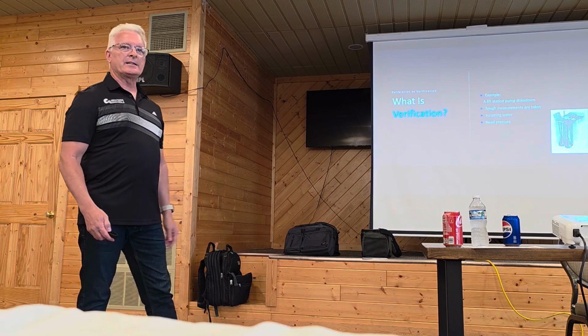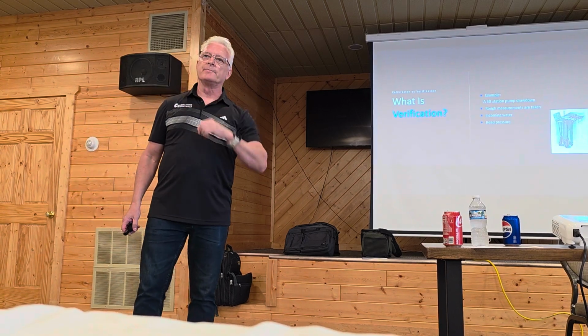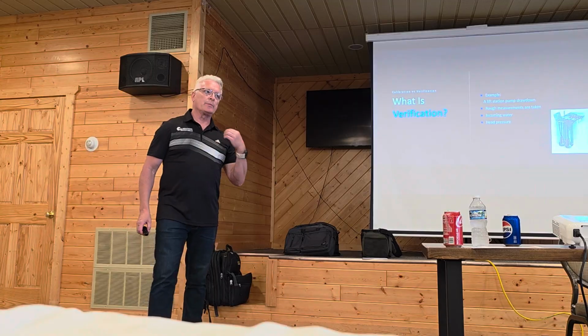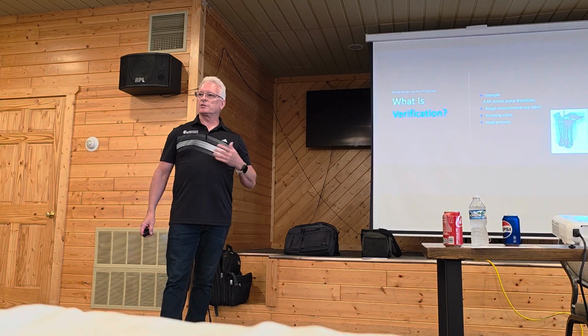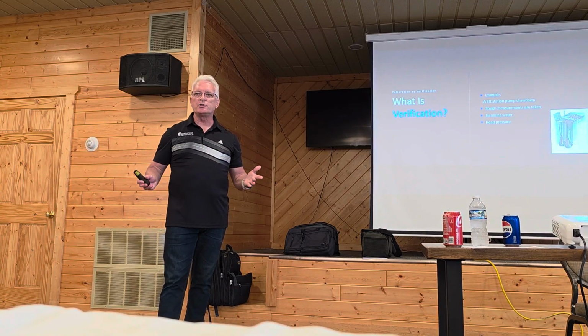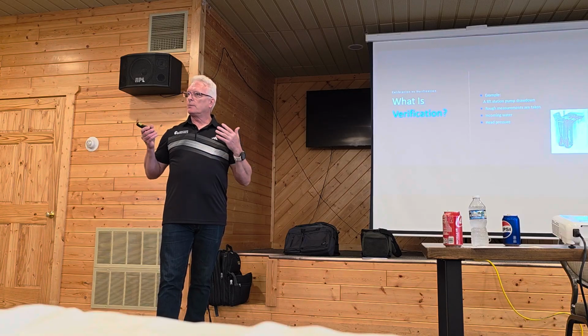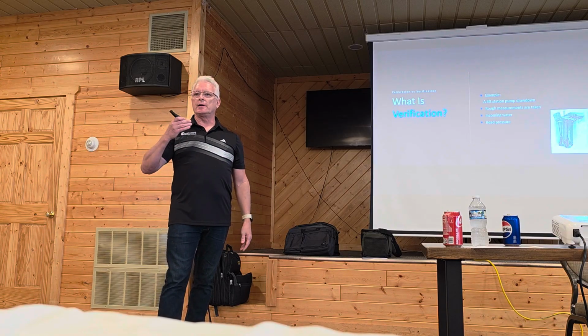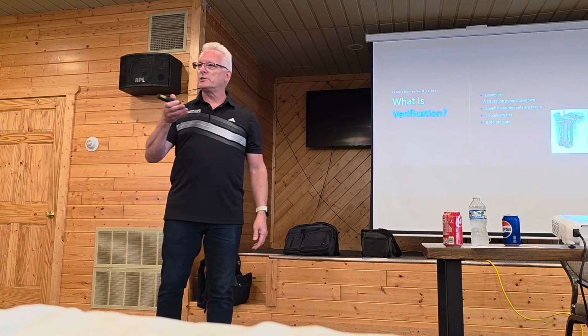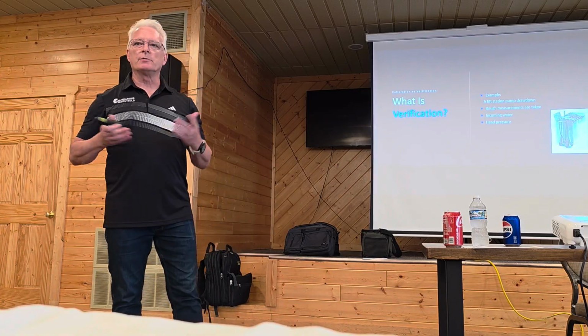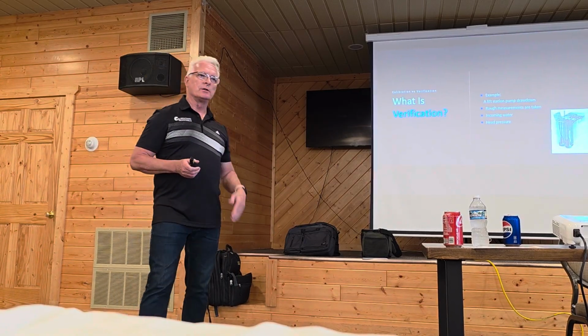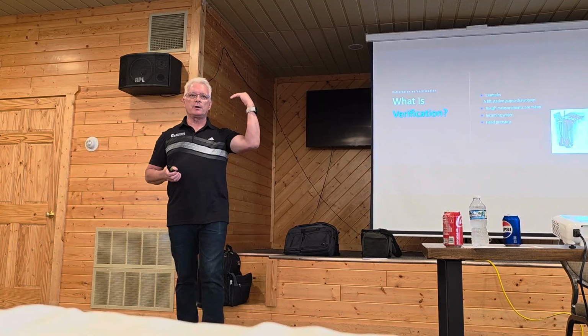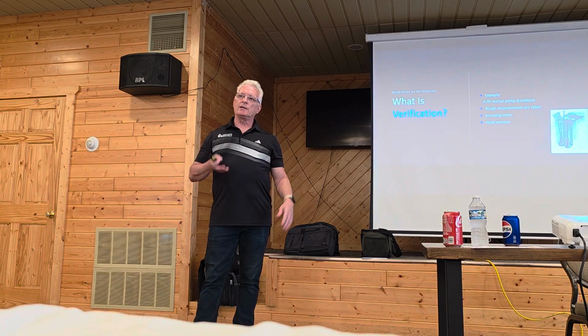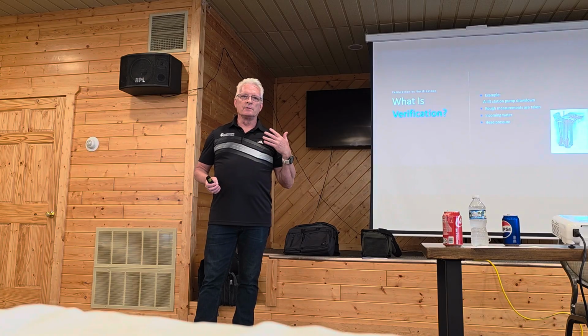So what is a verification? We talked about calibration versus verification. If you were to ask me, I'd say a verification is something where you really can't change anything. You're just checking it the best way possible so you can make the most educated decision about the result. So a lift station, for example, has pumps that are pumping, but there's no flow meter. So how do you know what's going through there? Well, you use that drawdown.